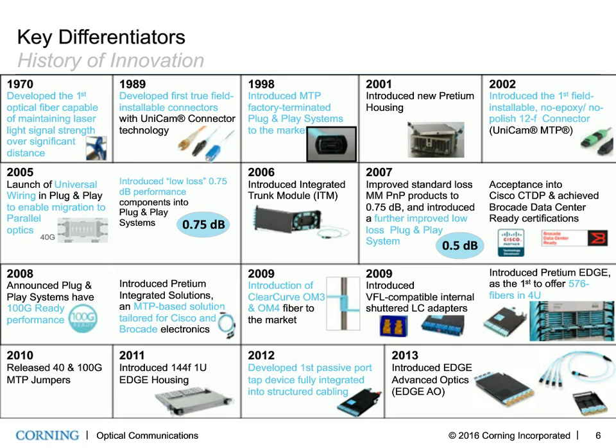And then in 2009, the game was changed again with the advent of bend-optimized fiber, multi-mode fiber you could bend and exhibit no bending loss. As a result of that key fiber development, and a lot of voice of customer, we were able to change the landscape of how data centers are deployed with our EDGE platform. Now you had a platform where you could pack things in extremely tight, and you didn't have to worry about fiber bending affecting performance.